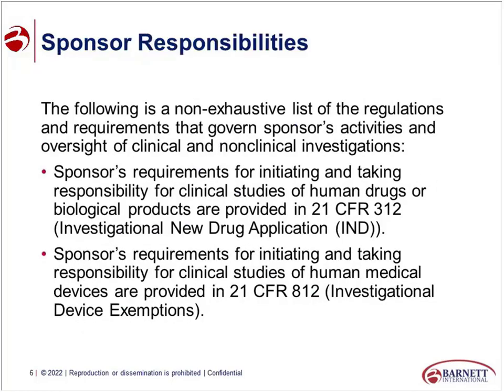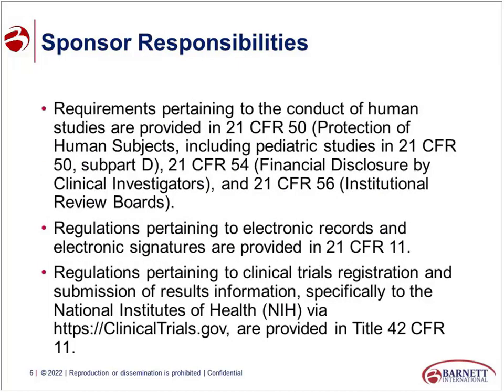The FDA talks about sponsor responsibilities — they inspect what they expect. You're responsible for initiating and taking responsibility for clinical studies of drug, biologic, or medical device products. We need to ensure informed consent is obtained in accordance with 21 CFR 50, and for pediatric populations, have plans for Subpart D. Any electronic records generating, moving, transmitting, creating, storing, or archiving regulatory data must be compliant with 21 CFR Part 11.